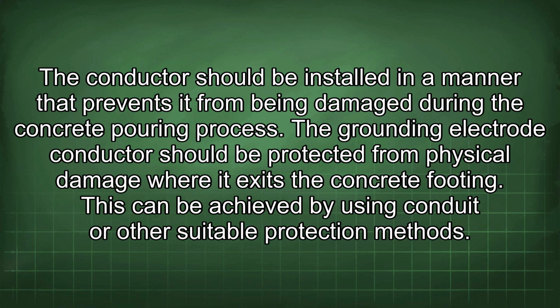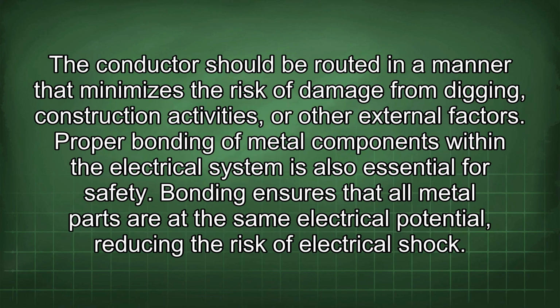The grounding electrode conductor should be protected from physical damage where it exits the concrete footing. This can be achieved by using conduit or other suitable protection methods. The conductor should be routed in a manner that minimizes the risk of damage from digging, construction activities, or other external factors. Proper bonding of metal components within the electrical system is also essential for safety.